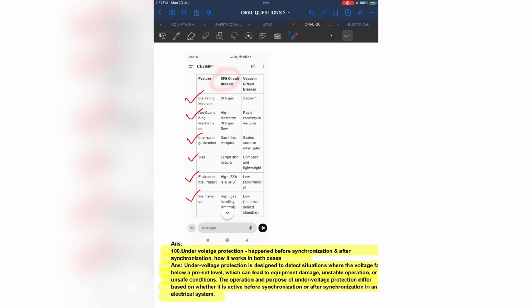Okay, in an SF6 breaker, arc quenching is done by a high dielectric gas, and here in a vacuum breaker we are using the vacuum interrupter for the arc quenching. The SF6 breaker is a gas-filled, complex design, while the vacuum breaker uses a sealed vacuum interrupter. As for size, the SF6 breaker is very large and heavy, but the vacuum circuit breaker is compact and lightweight.